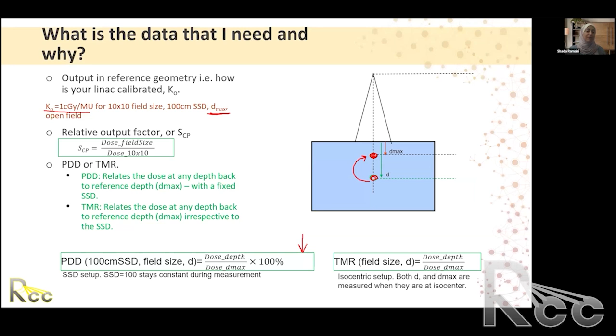And because we have deviated from the way we calibrated our LINAC, and in this example, it's Dmax, then we need some sort of correction factor to take it back to Dmax. And that correction factor is either PDD, percentage depth dose, or TMR, tissue maximum ratio. And both are equally good, and you can use both of them. Most of the time, I have encountered that people are comfortable with using percentage depth dose. So moving forward in our examples, I'll be giving PDD, but both are equal. The idea here is I need some sort of a correction, right? To take the clinical treatment depth, this is where the patient is being treated, back to the reference depth, which is Dmax, wherever your output factor is defined at.